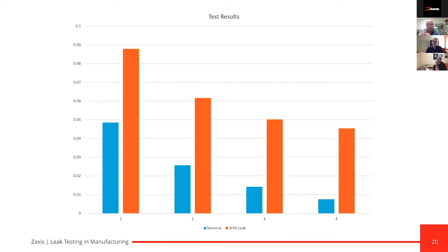The first shot is what we'll refer to as a virgin test. But if you're doing some setup and some repeatability testing, if you did run the test multiple times back to back, you would find that the results for that part would get better and better, because what you've done is you've stretched it to a point where, in that finite set amount of time, let's say for example you had 3 seconds of fill, the first time you test it, you give it that 3 seconds to continue to expand and get to a certain point.